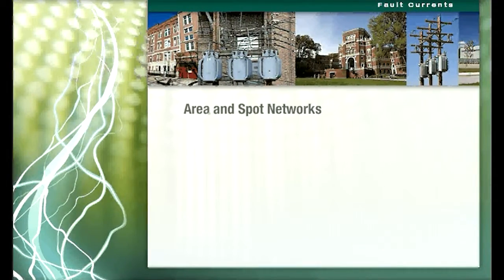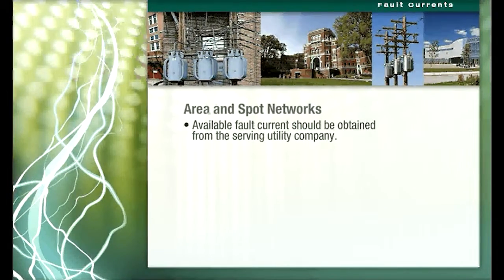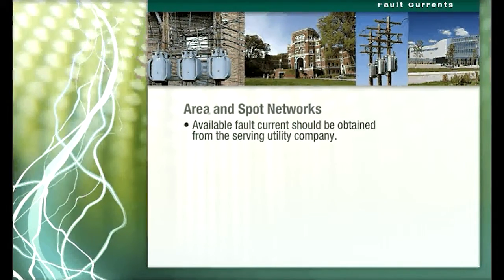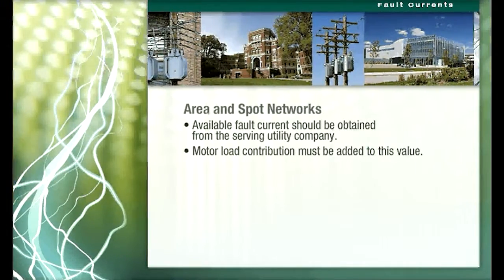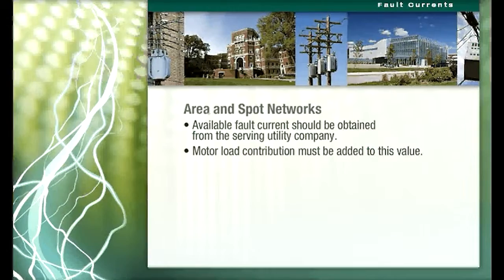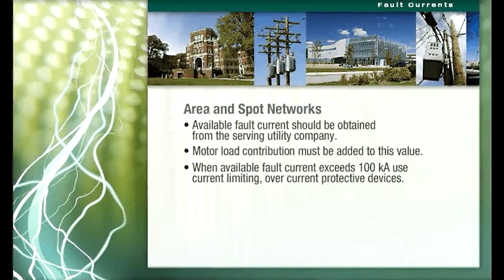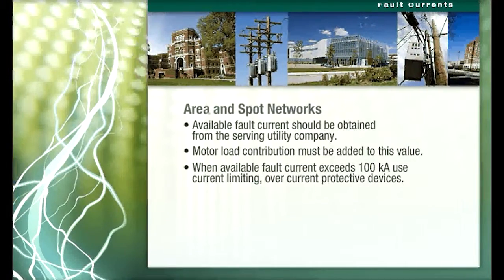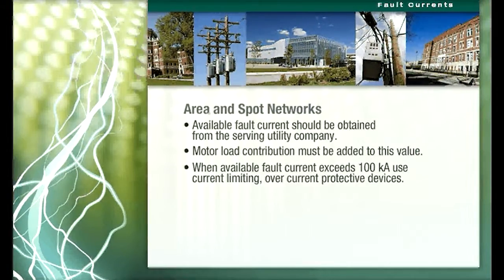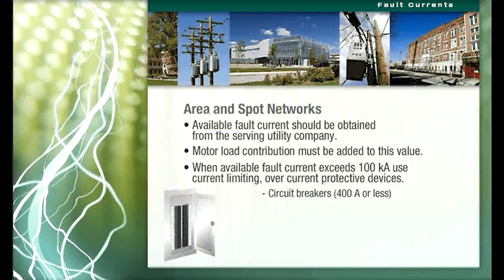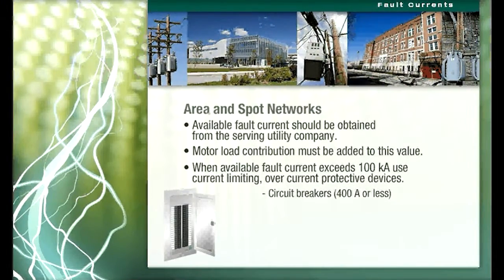For services derived from area and spot networks, the available fault current at the service should be obtained from the serving utility company. Keep in mind that motor load contribution must be added to this value. For area and spot network services, the available fault current can exceed 100 kA. In these cases, it is common practice to apply current limiting overcurrent protective devices. These devices can be circuit breakers when the rated current is 400 amps or less.